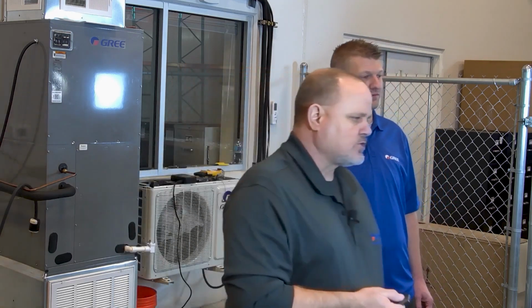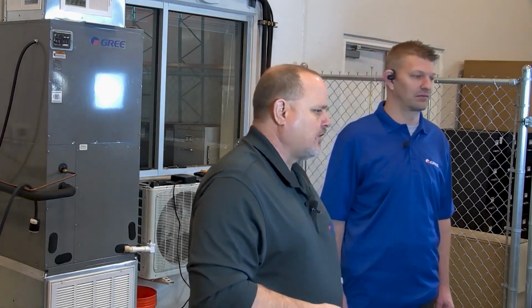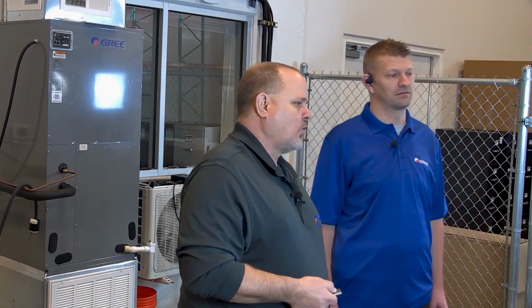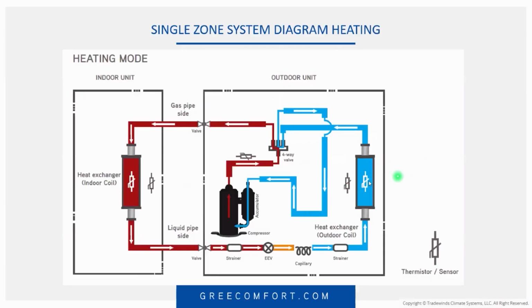Because any basic refrigeration circuit is going to have a compressor, an indoor coil, an outdoor coil, and a metering device. Those are your four major components that you have to have. All we do in mini split technology is build on that. Especially, all we do is heat pumps. We don't even sell cooling-only models. They make them, we don't sell them. The only difference is we're adding in that reversing valve so we can have flow in both directions and actually provide heating mode or cooling mode, okay?